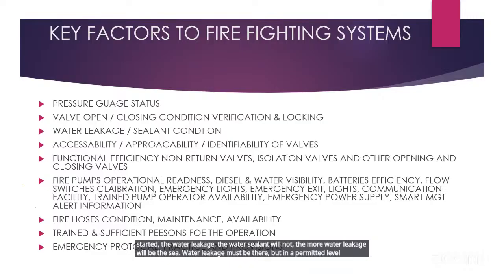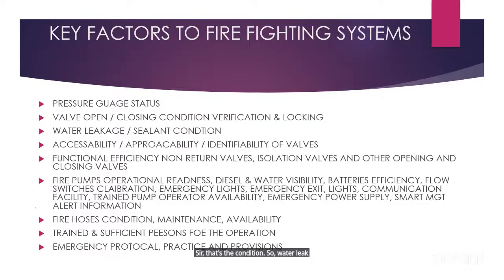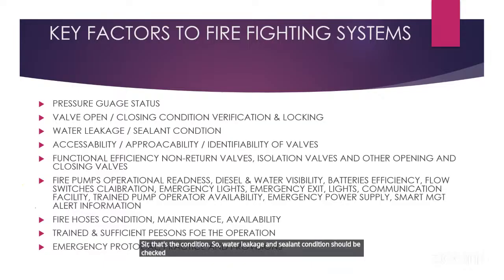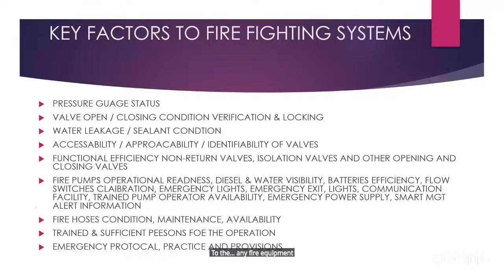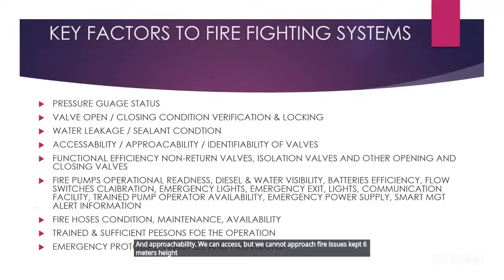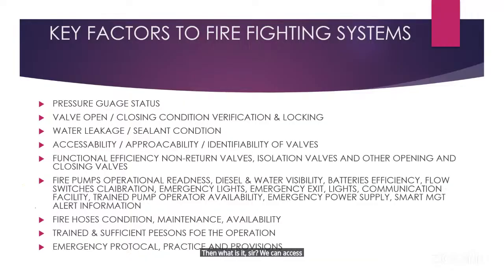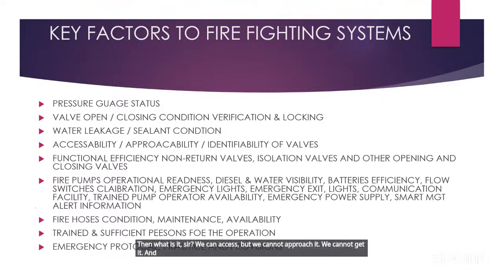So that's the condition. Water leakage and sealant condition should be checked, and accessibility to any fire equipment. Accessibility must be there. And approachability: we can access, but we cannot approach. A fire extinguisher is kept at 6 meters height. We can access, but we cannot approach it, we cannot get it. And identifiability of valves is another important thing.